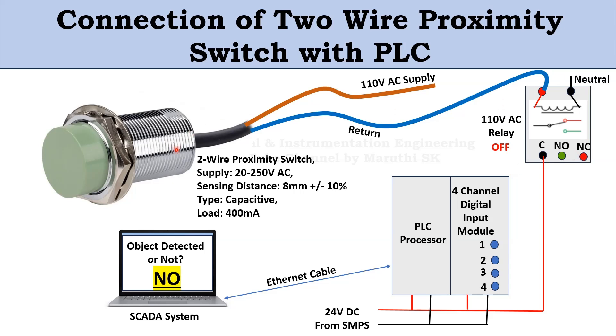We have connected the proximity switch to a relay. The brown wire is connected to the phase and the blue wire returns to the phase, both connected to a 110V AC relay coil. The relay has a common contact, normally open, and normally closed — black for common, green for normally open, and red for normally closed. The PLC processor is connected to a 4-channel digital input module. 24V DC is applied to both the PLC processor and the digital input module, and also extended to the common terminal of the relay.